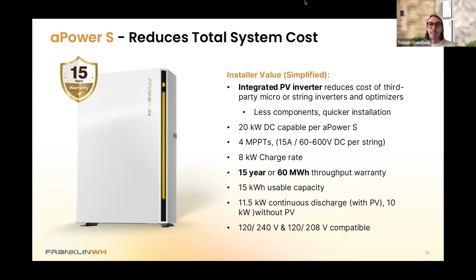The continuous output of aPower S is 11.5 kW when the solar is producing. However, it does revert to 10 kW continuous at nighttime or if there's no PV available. And then another unique thing about Franklin WH is our batteries are 120/240 volt compatible as well as single phase 208. So if you are coming across any type of multifamily housing or that 120/208 single phase distribution, the Franklin whole home batteries can support that.